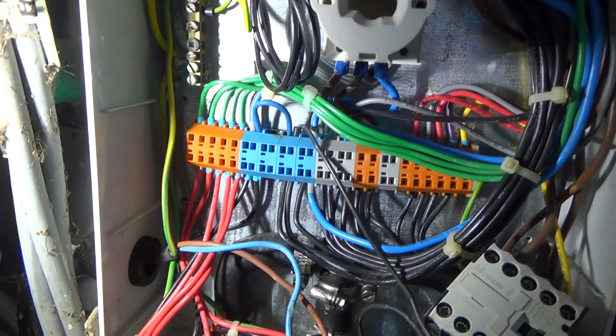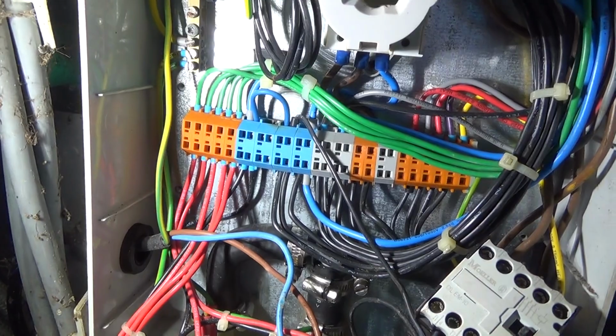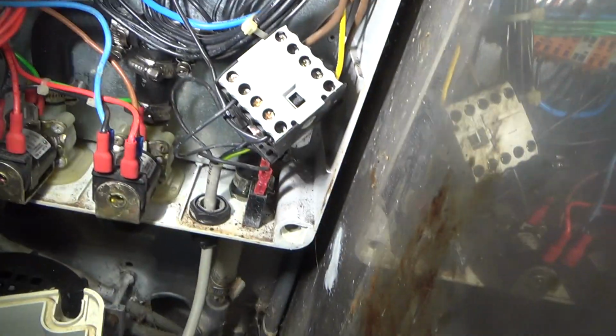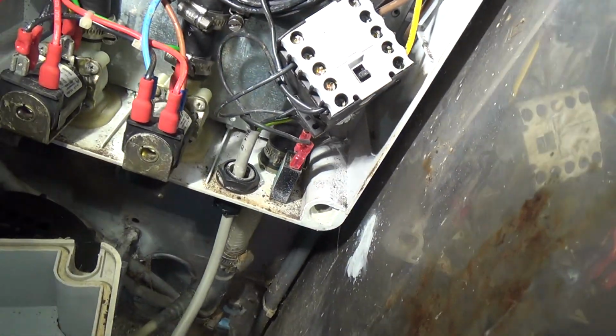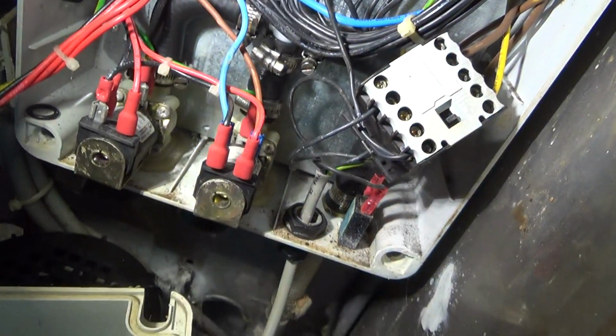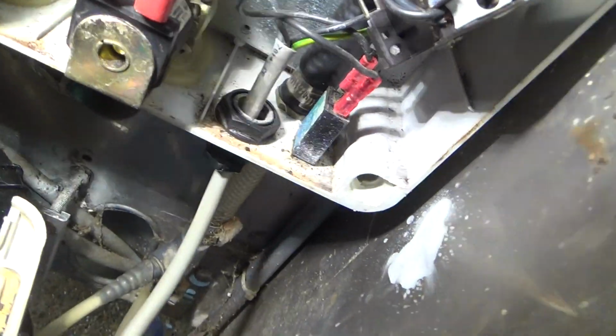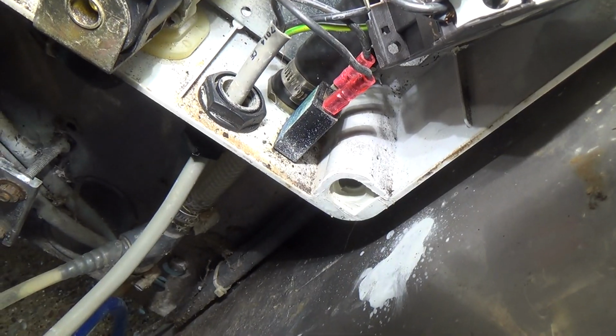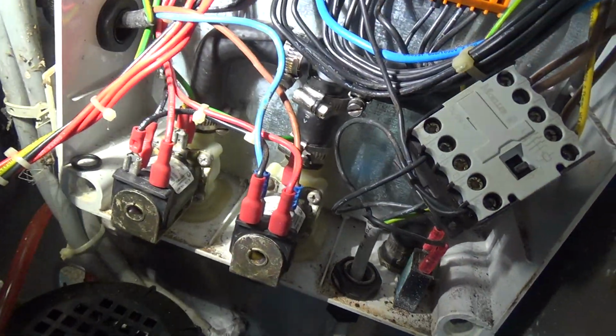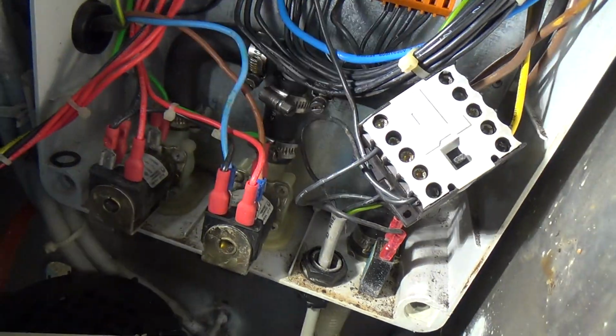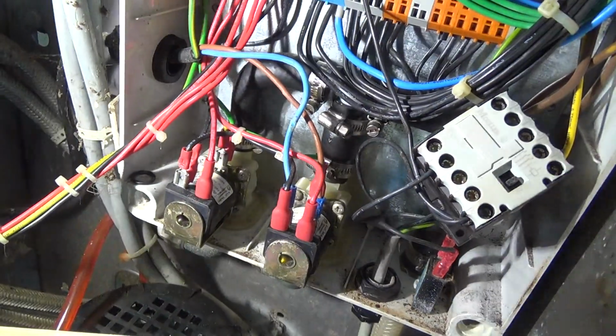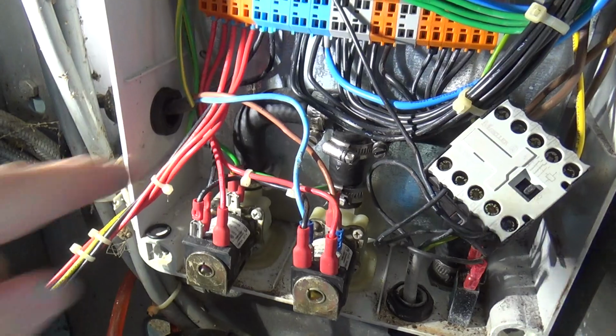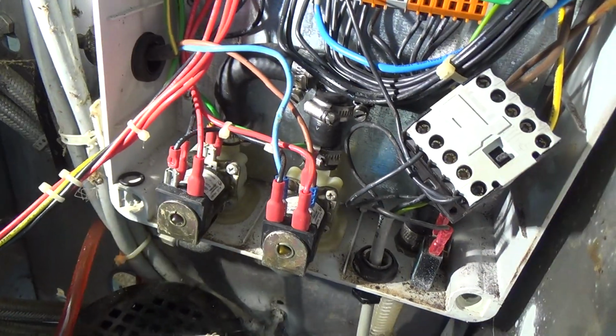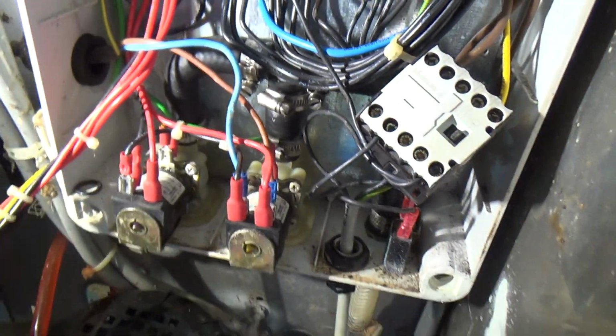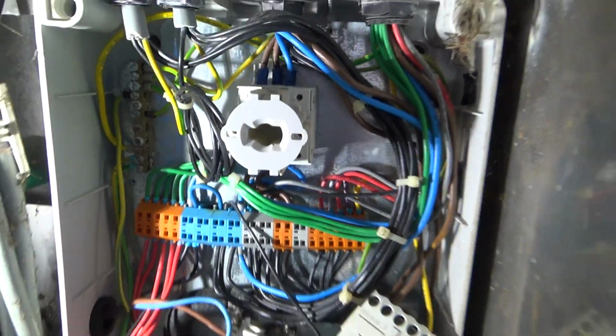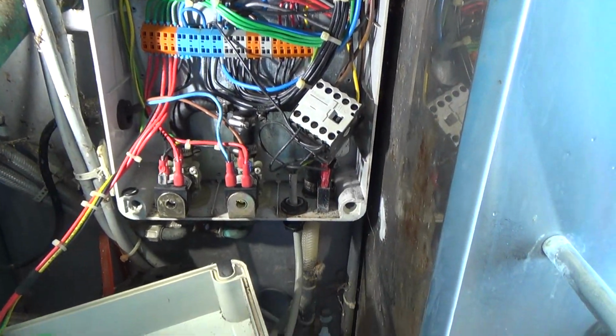So you think blue would be neutral, but it may not be. Oh no, it does go into the coil connector, so it probably is the neutral. It does look a bit suspect down there, because I can't think of it happening recently, but you could get a water leak on one of these hoses. But if it had, the box would be wet. Anyway, enough whittering, let's get the Megger going.